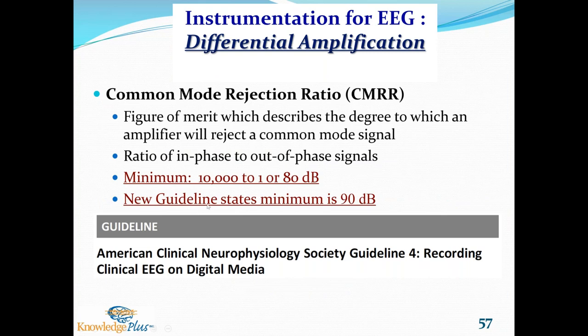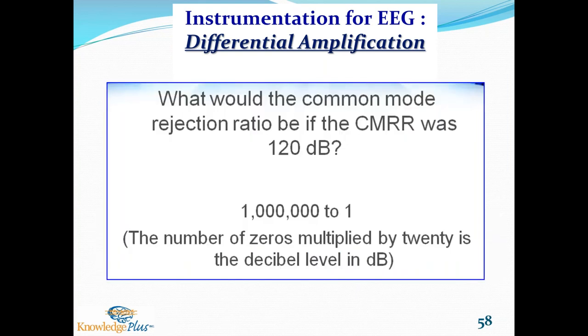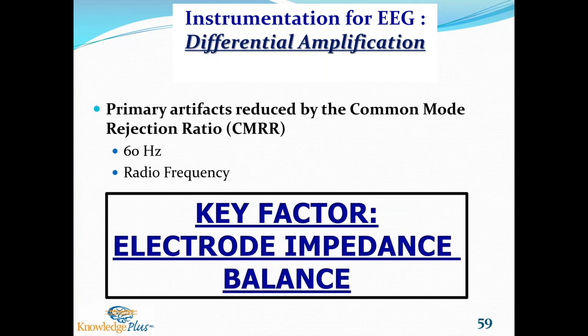Now, in an older guideline, it stated that the minimum common mode rejection ratio should be 10,000 to 1 or 80 dB. In the new digital guideline, it states the minimum is now 90 dB. The common mode rejection, if it were set at 120 dB, is 1,000,000 to 1. And the primary artifacts that are gotten rid of with this ratio are 60 hertz and radio frequency noise. The key factor in getting rid of artifacts is electrode impedance balance.